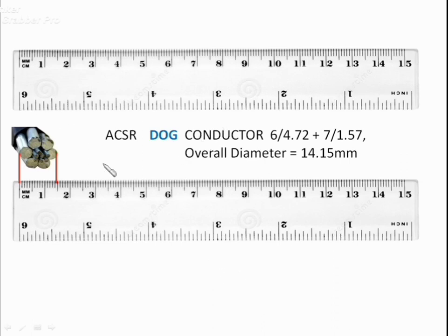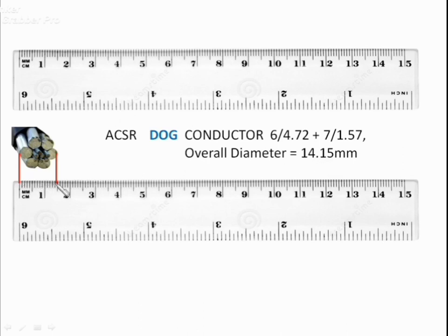To identify a conductor, we can measure its diameter using a scale. For the Dog ACSR conductor, its diameter should be 14.15 mm. Using a 15 cm scale, we can measure it and see 14 mm clearly. That is how a conductor can be identified.